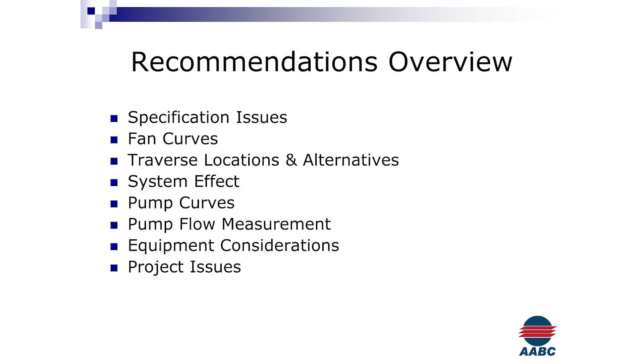Some of the things I want to look at specifically are specification issues, fan curves, traverse locations or alternatives. Some of you may be really surprised at how hard it is to get an accurate, repeatable traverse sometimes, whether it's because of obstructions or elbows upstream or downstream of where we're taking our traverse.